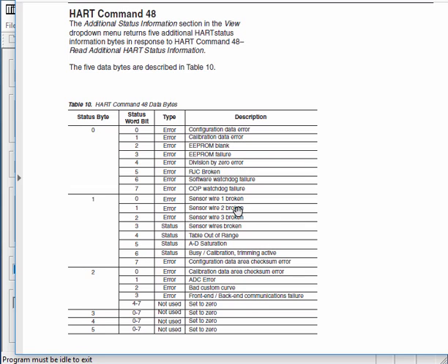So if the technician were to go up there with a new sensor, or at least he knows what he's looking for in the first place, he doesn't have to go up needlessly all the way up a stack, which could be dangerous, and depending on weather, might not even be able to get it done in one day. So there you have it. That's if you have the good documentation from the manufacturer of the HART slave.